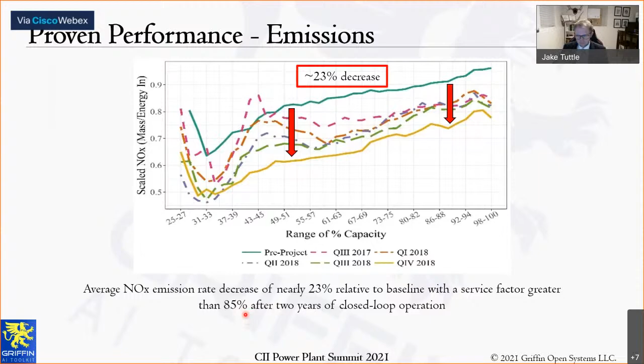What you see here is quarterly averages across the unit's load range of emission rate. When we began, this is the dark green line; towards the close of our project, this is over 2 years of the system self-learning and self-adapting as more operational data is collected. In total, about a 23% decrease across the entire unit's load range, from minimum load at 25% of maximum capacity to 100% capacity. The other key thing here is the system had a service factor of over 85%, meaning it's doing this nearly all the time.